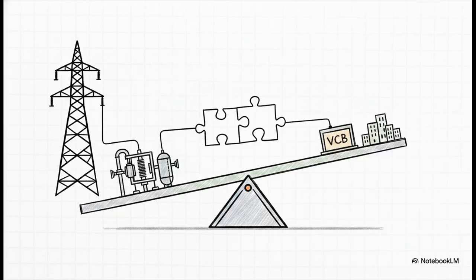Now, an absolutely crucial point to remember here is that neither of these technologies is universally better in some absolute sense. Real grid engineering is all about matching the exact right technology to the specific voltage tier and the specific environment. You can't just slap VCBs everywhere because vacuum interruption simply doesn't scale safely or efficiently to extreme transmission voltages. And on the flip side, you definitely can't put GIS everywhere because SF6 gas systems are expensive overkill for a standard local distribution substation. You really have to use the right tool for the right tier.